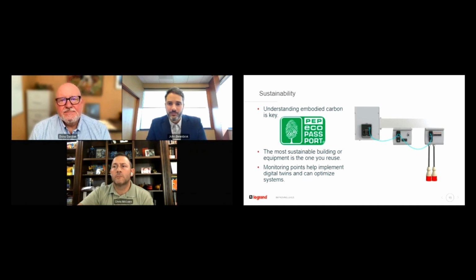If you look at busway, for example, building on what Chris said, busway is a reusable product and it's voltage agnostic - it's a low voltage standard up to 600 volts. So if you're at 208 voltage now, you can easily reuse the busway at 400 or 480 volts to start getting your power to where it needs to be.